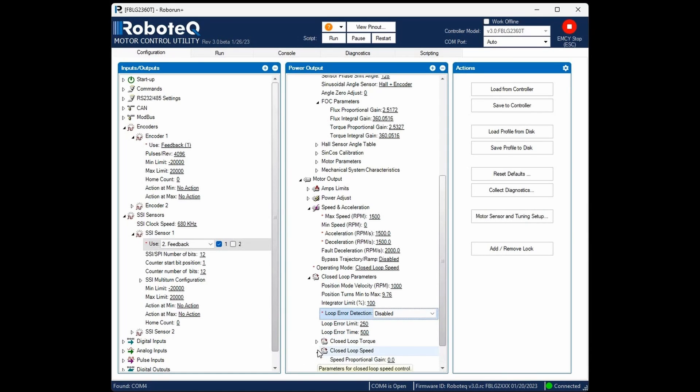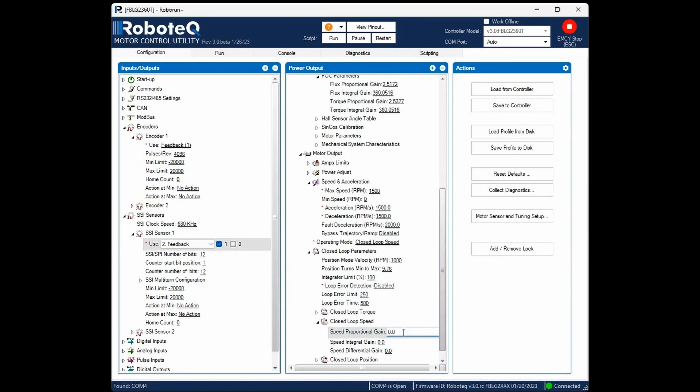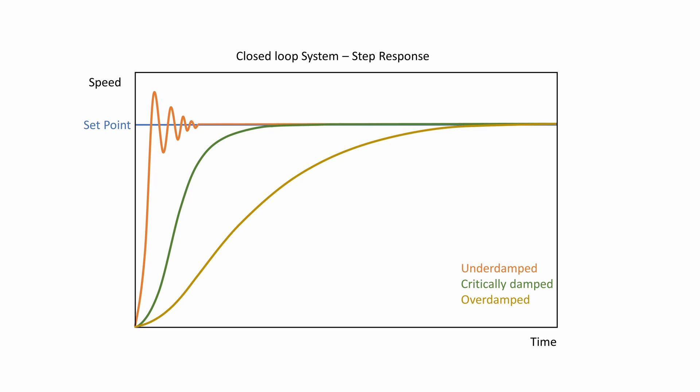Next, set the closed loop speed PID gains. Finding the optimal PID gains is part of the motor's PID tuning process and should be carried out when the motor is operating under its nominal load, as the system characteristics vary under different load conditions. This topic will be covered in another video tutorial.